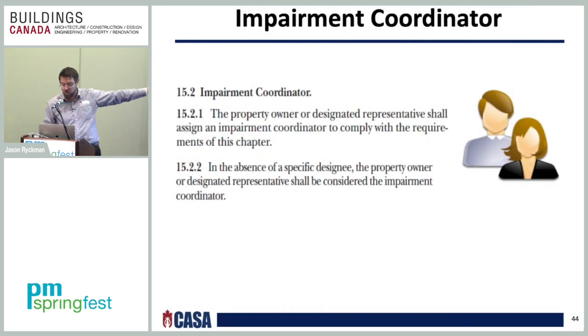Okay? So the impairment coordinator, it's actually in the standard, 15.2. It says the property owner or designated representative shall assign an impairment coordinator to comply with the requirements of this chapter. In the absence of that, if there isn't any, the owner or owner's representative has to take that place. And that's in the standard when using the NFPA 25 document.